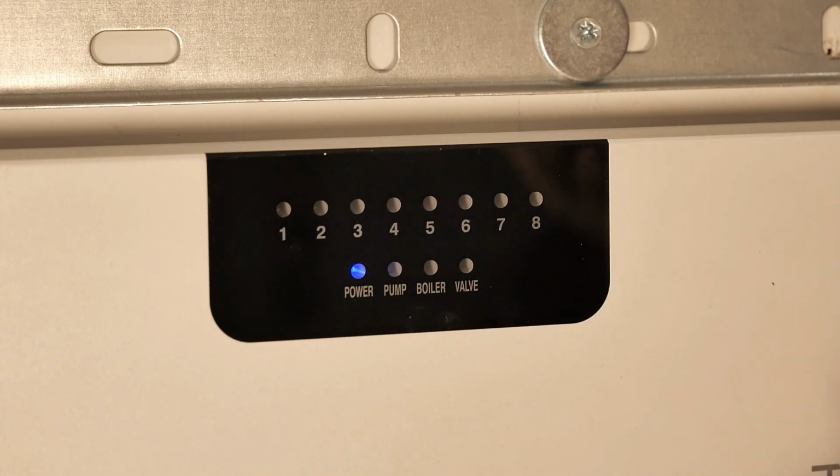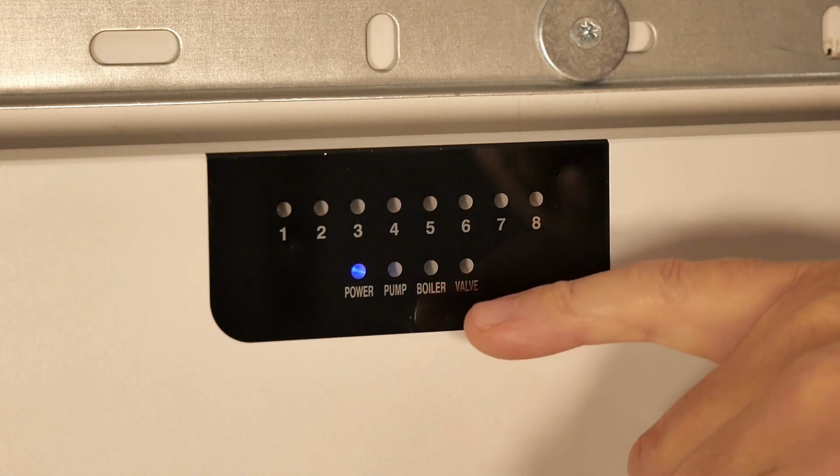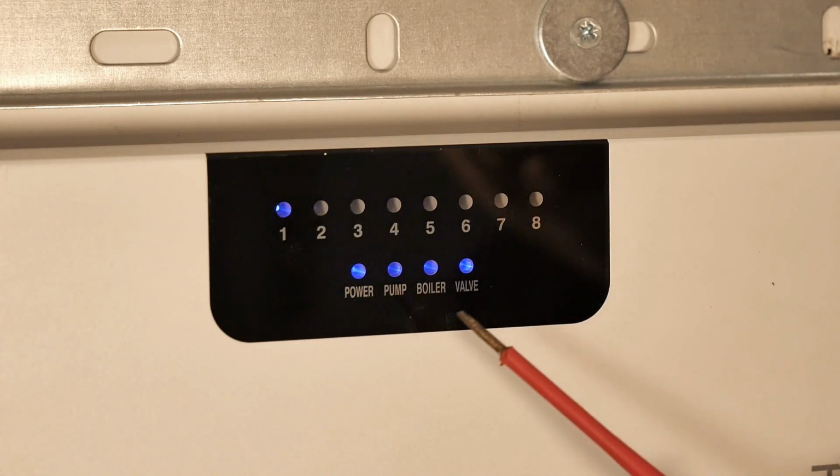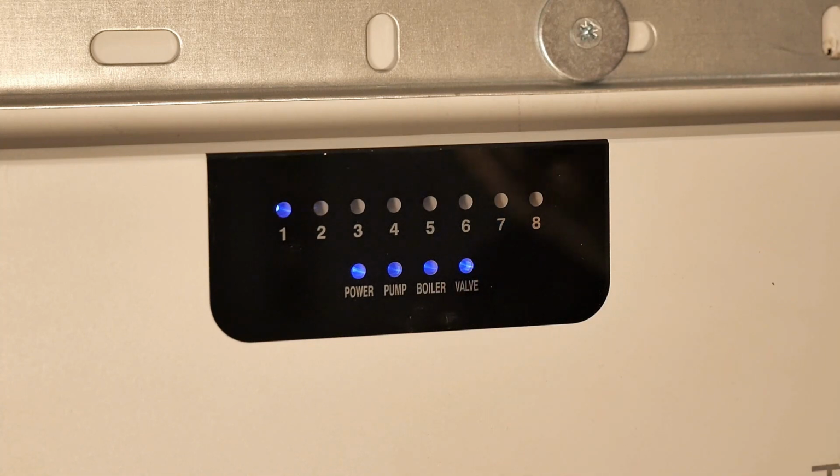There is a dip switch that we can show you inside, which delays the boiler and the pump demand until the valve is fully opened. But for this instance we'll just instigate room demand now, and there we can hear the click. So zone 1 is calling, and it's calling for boiler, pump and, if you were to have one, an optional zone valve.